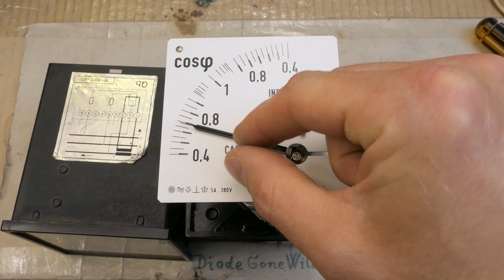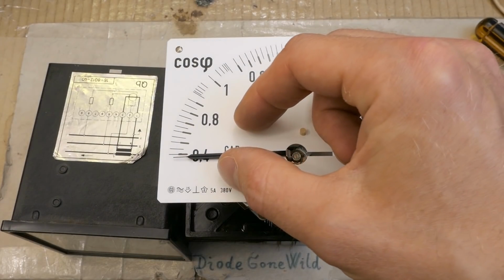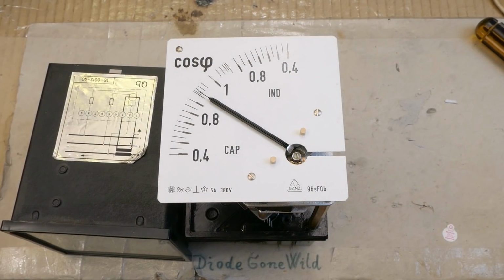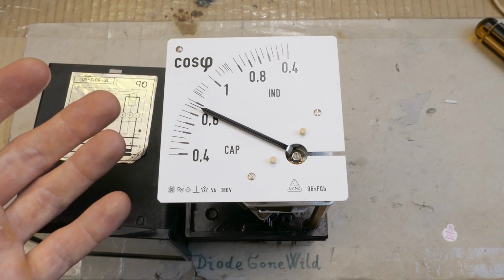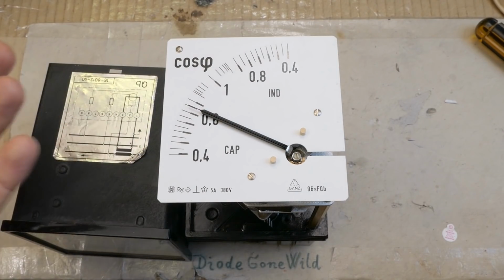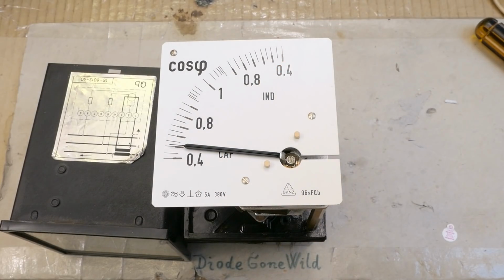So if there is no load or not enough load, it just shows a random reading, or it just indicates the last state. So it probably has to be used together with a current meter to verify that there is enough load for this to indicate.